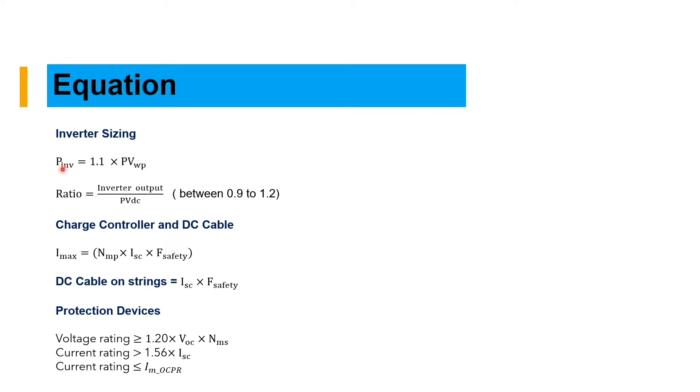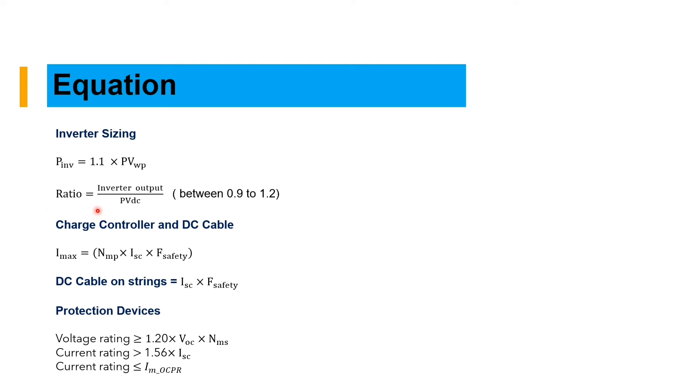The inverter is sized based on 1.1 times PV array size. And the inverter sizing ratio should be between 0.9 to 1.2 to avoid losses.